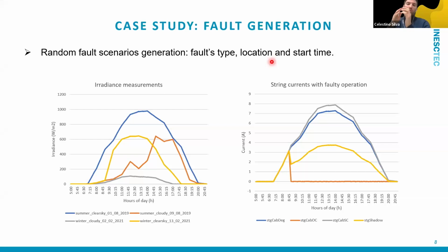To observe the differences between each fault type, a clear sky summer day was chosen to make these differences more noticeable. Additionally, the same fault start time and location were selected for a better visualization of the graphics. These rules can be observed in this image that represents the string currents for each fault type. As we can see, until the fault happens, all fault types present the same behavior, and after a fault happens, the string currents have different behaviors according to each fault type.